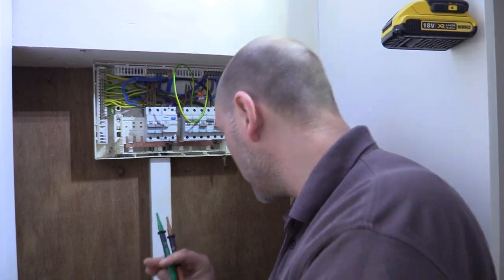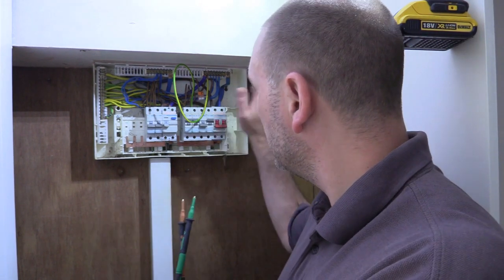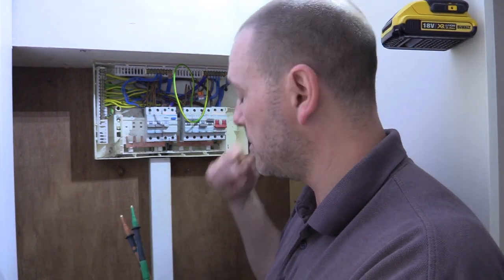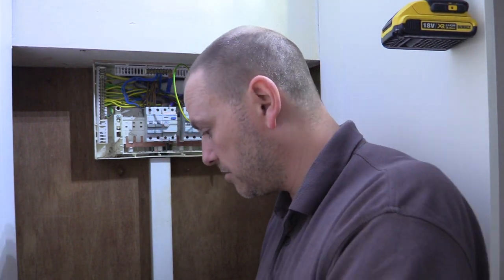They've got like a nice wooden flooring, and it's not worth it. I can do a nice surface run, and I can hide it and blend it in. We've got a route, we're going to do that. We also need to run in some power for a TV point later anyway, so we might as well keep the same route. So boiler circuit's out of the question really. I'm going to remove the neutral and the CPC off that circuit in a sec before I test, because it might throw up anything. So let me just pause you while I do that.